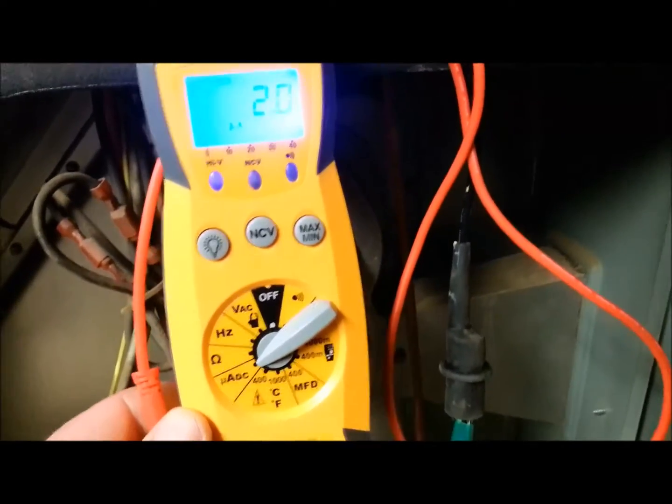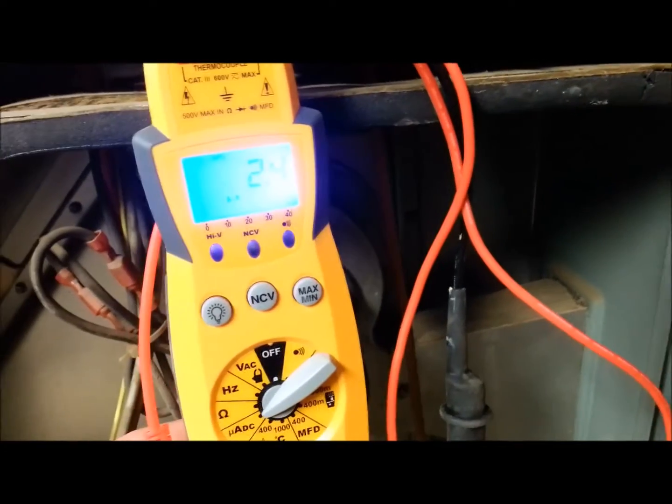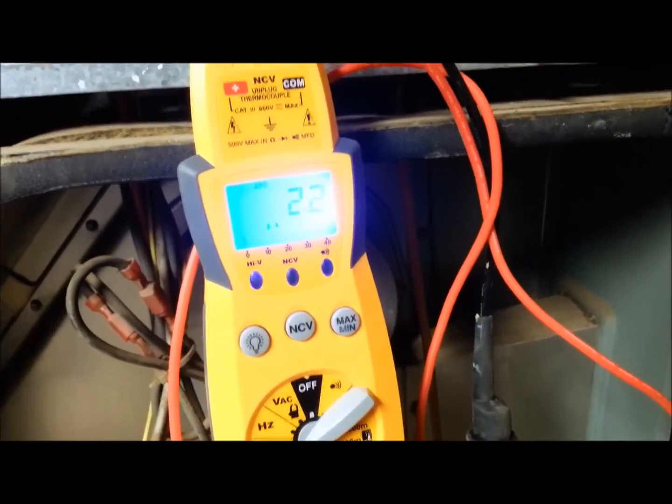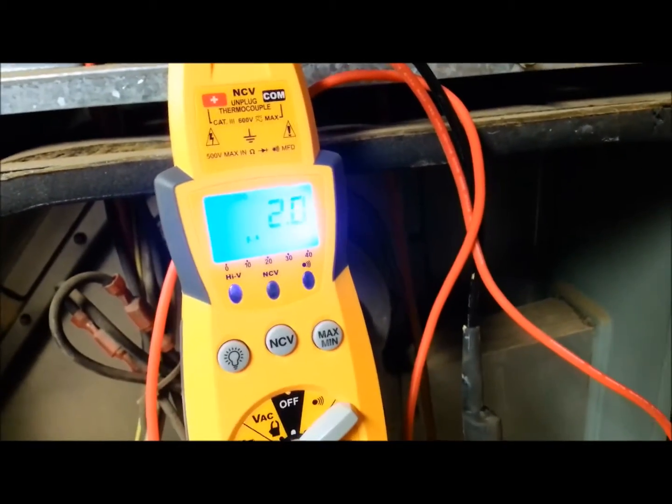So this flame sensor could be cleaned. I'll go ahead and clean it and then we'll retest it, see what we come up with. Reading 2.5, it'd be better reading closer to 3.5 to 4, so we'll clean it, see what we get.